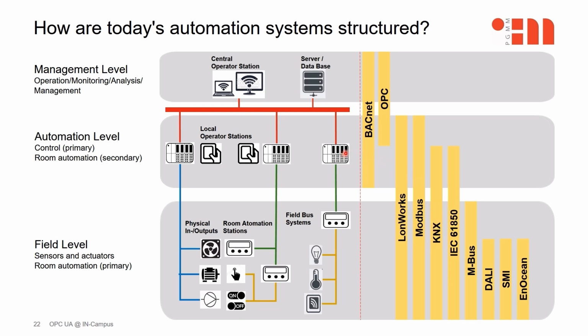The controllers of the automation level communicate with each other and with the devices and operator stations at the management level via a central automation bus. BACnet is primarily used as the communication system for the automation and management level. However, it cannot be omitted that LonWorks as well as Modbus, KNX or IEC 61850 will be used on the automation and management level. OPC is generally only used in the field of building automation for coupling with third-party systems or with SCADA systems.